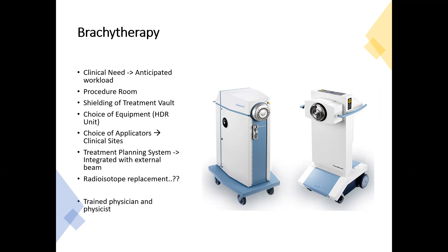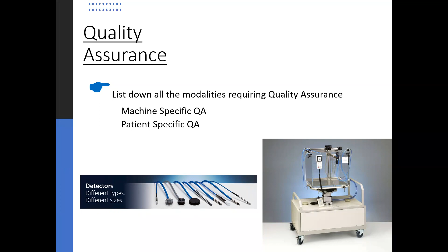When we speak about the quality assurance, the first important thing is, please list down all the modalities which you have at the moment and which you are anticipating in near future, and then write down the QA equipment required for all those modalities. So we know there is a requirement of machine specific QA, and then there is a requirement of the patient specific QA. We all know that if we are going to have a good linear accelerator, certainly everyone needs a 3D water scanning system. And definitely we need a set of ionization chambers for absolute measurements and scanning, and certainly the electrometer. This is the minimum thing we need for the scanning and the absolute dosimetry.